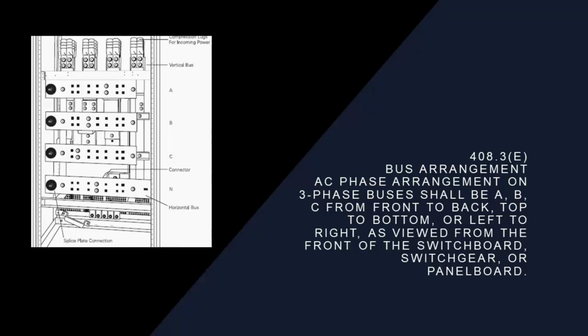408.3(E) is about the bus arrangement. AC phase arrangement on three-phase buses shall be A, B, C from front to back, top to bottom, or left to right, as viewed from the front of the switchboard, switchgear, or panel board. So that is absolutely going to be a homework question, and almost certainly going to be a question on your final as well. This question comes up all the time with IEC materials.